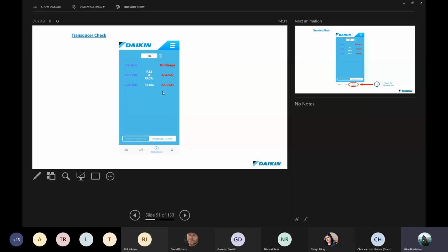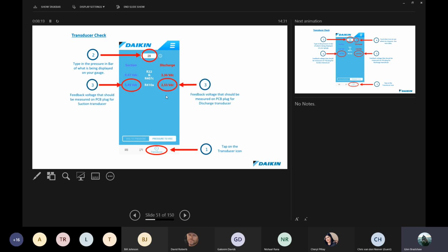Okay, so pressure transducer. Again, your options here, you can either do voltage to pressure or pressure to voltage. If you put in a value, doing the pressure to voltage, then it will kick out a voltage over here. So here we've entered a pressure and here we are now going to get a voltage out. And remember, what you're testing, you need to remember whether you're doing a suction or discharge. You'll see the values are different.